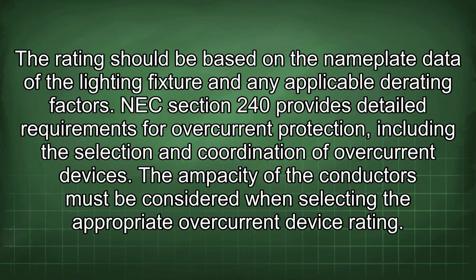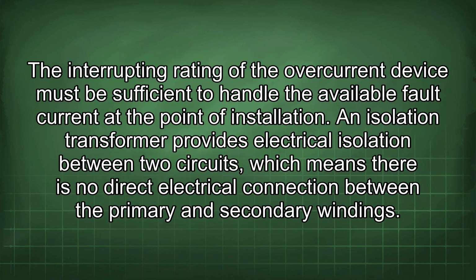NEC Section 240 provides detailed requirements for overcurrent protection, including the selection and coordination of overcurrent devices. The ampacity of the conductors must be considered when selecting the appropriate overcurrent device rating. The interrupting rating of the overcurrent device must be sufficient to handle the available fault current at the point of installation.